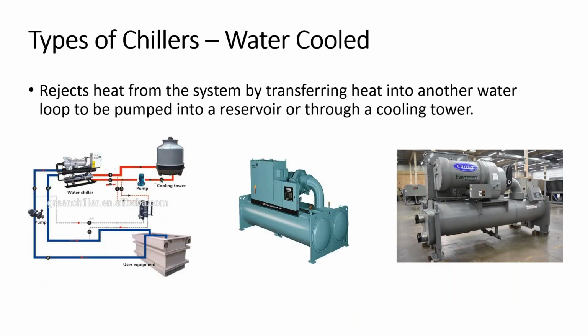The other option is water cooled, where you take the heat from whatever you're pulling it out of, the building or process equipment, and pump it through the chiller. The chiller removes the heat from the water, puts it into the condenser, which pumps into another loop through the cooling tower to reject it. These pictures show different machines, and we are equal offenders here. So there's a York in the middle and a Carrier on the right. But these require piping for both the chilled water and the condenser water versus the air cooled where you only have the chilled water loop.